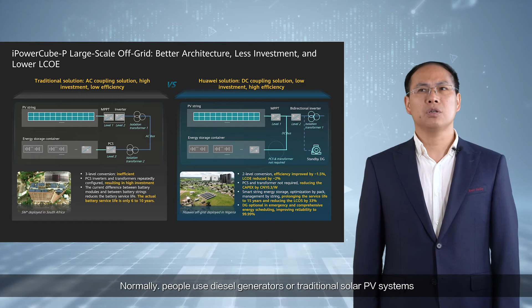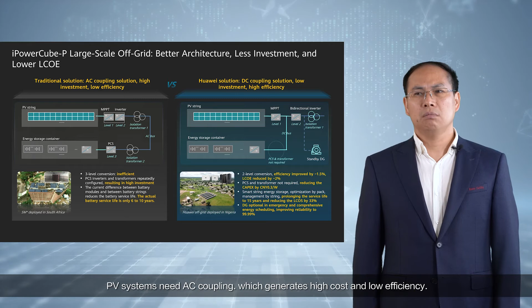Normally, people use diesel generators or traditional PV systems to supply power in those scenarios. PV systems need AC coupling, which generates high cost and low efficiency, as it needs three-level conversions, more than one set of PCS and transformers, and storage systems whose service life is short.